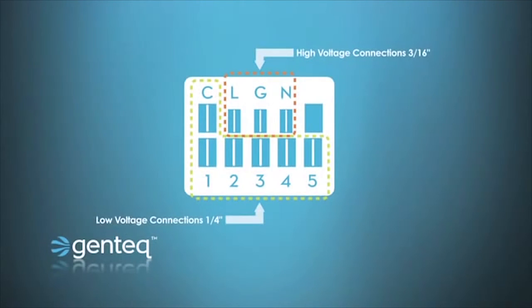So now that we know how the X13 can be programmed and what each one of the connections on the motor does, let's look at how the wires are connected to the motor. You'll notice from this picture that the high voltage L, G, and N terminals are actually smaller than the low voltage connections, the C and the 1 through 5. This was done on purpose so that a high voltage wire could not be put on a low voltage connection, which would be bad for the motor.